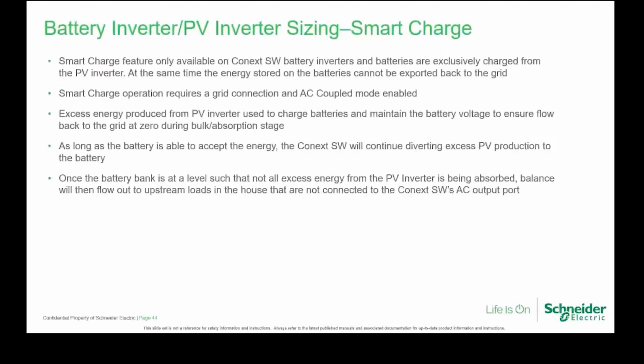So smart charge is basically only available when it connects XW inverters and batteries are exclusively charged from the PV inverter. At the same time, the energy stored in the batteries cannot be exported back to the grid. So basically it just matches what's coming into the battery, and then it starts running the SW so that it doesn't export anything back out to the grid. It does require a grid connection and AC couple mode enabled. Basically, it allows excess energy from the PV inverters to charge the batteries and maintain the battery voltage, to ensure flow back to the grid is zero during your bulk and absorption stage.